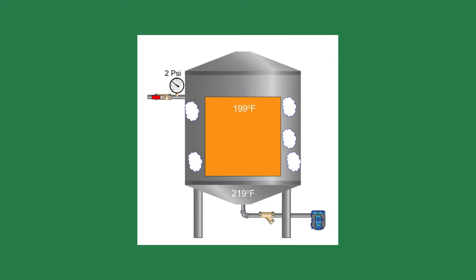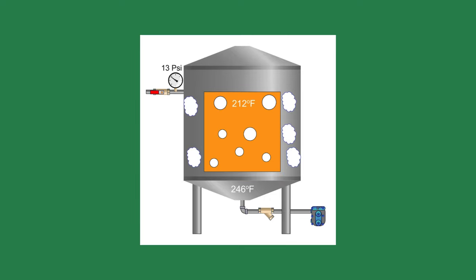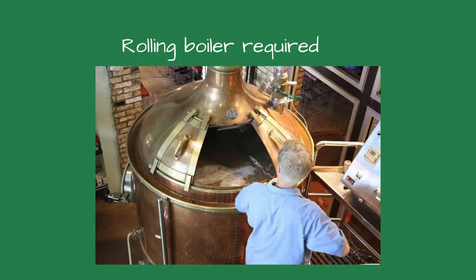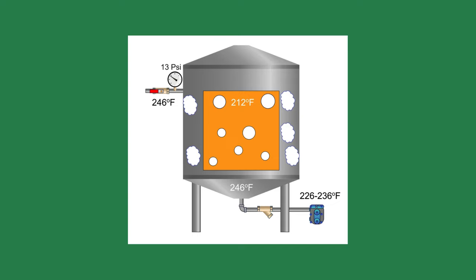It could eventually cause the water to boil, but it will take a long time. Conversely, steam at 13 psi is 246 degrees, or about 34 degrees higher than what we need. It will heat the wort much quicker and get it boiling much faster. The condensate temperatures of the steam system range between 10 and 20 degrees lower than the steam temperature. If the steam pressure is 13 psi, the condensate temperature will be between 226 and 236 degrees Fahrenheit.